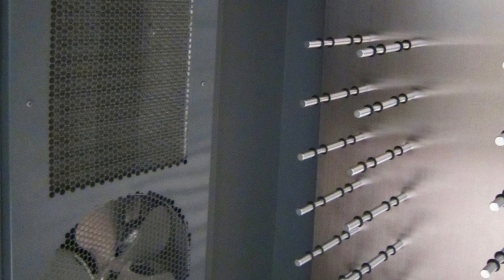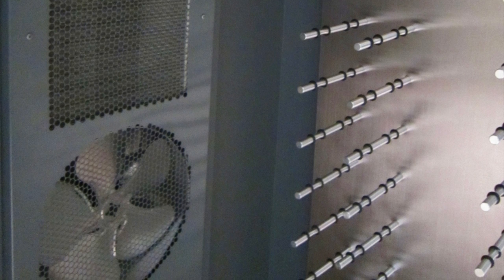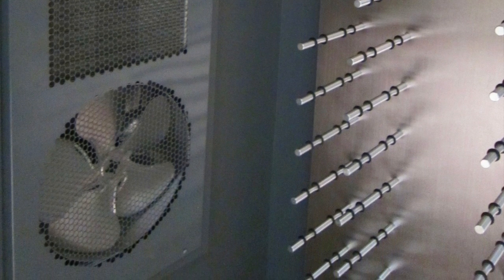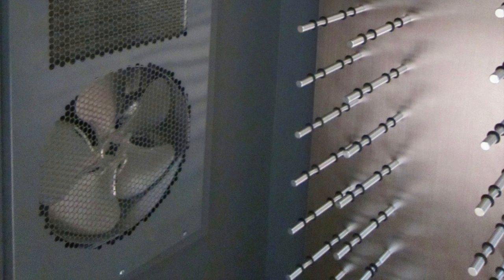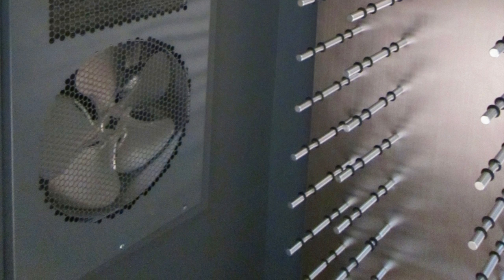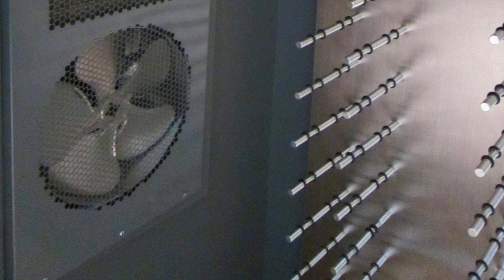Therefore, we had to run our lines down the inside of the adjoining elevator shaft and create a soffit in the lower level to run the lines across and out to the courtyard. The drain line also followed this route, and because of the up and down path, we also installed a condensate pump. A mini pump was placed right outside the cooling unit in the cellar.